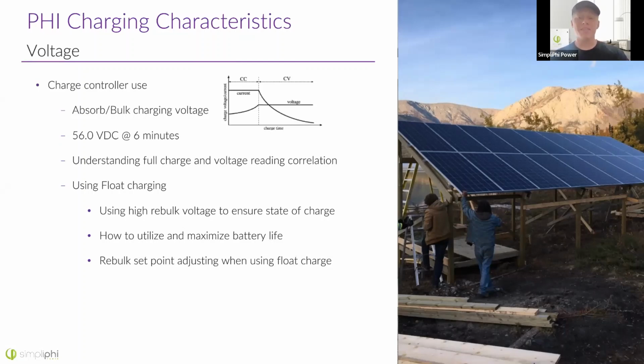Another place they may sit is at 54 volts. The reason being, if you've got PV coming in, we recommend programming the float voltage of your charge controller to 54 volts. Now, I would not bother floating your batteries if you're on grid, because if you are grid connected, using the electricity from the grid just to keep the battery topped off is a waste of energy. It's really not needed. The batteries don't discharge quickly on their own as a lead acid would, and they really don't require a float charge. So if you've got additional renewables coming in, you might as well use them and float that battery. Otherwise, don't worry about it.